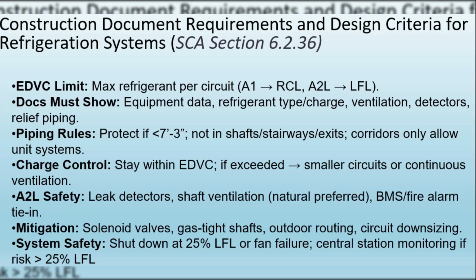This section lays out how refrigeration systems must be designed and documented for school projects. First, ASHRAE 15 introduces the concept of EDVC, the effective dispersal volume charge. It's essentially the maximum amount of refrigerant allowed in a single circuit so that, even if all of it leaks into a space, it won't create unsafe conditions. For A1 refrigerants, EDVC is based on concentration limits, while for A2L refrigerants it's based on lower flammability limits. Because A1 refrigerants are being phased out, all systems should be designed with A2Ls.